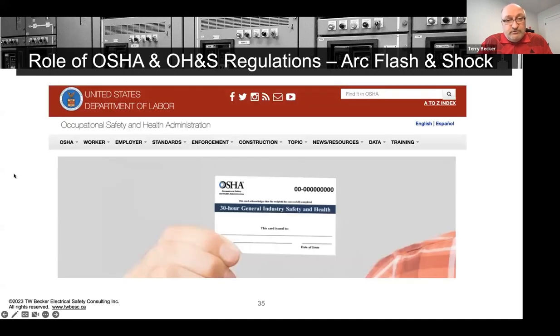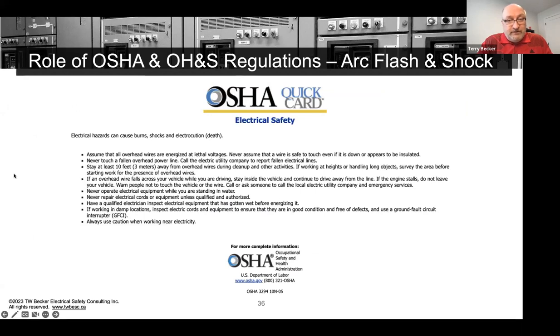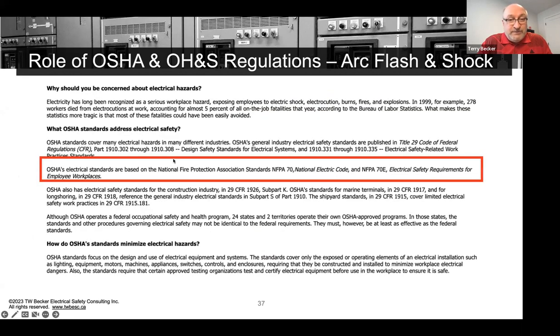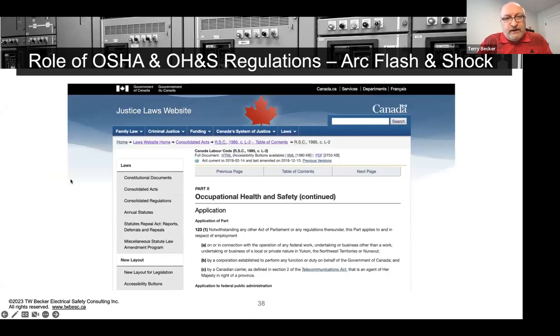So I do have just, go to the internet, check OSHA's website. They have electrical safety content. And I found this page where they do indicate that their documentation is really referencing the National Electrical Code and NFPA 70E. They haven't formally adopted 70E into OSHA law, but their language, their documentation, the regulations really align with it if you read between the lines, right? And then in Canada, federally, we've got the Canada Labour Code Part 2, which is very high level. It only has general duty. The electrical safety section is quite outdated in Canada's federal laws.